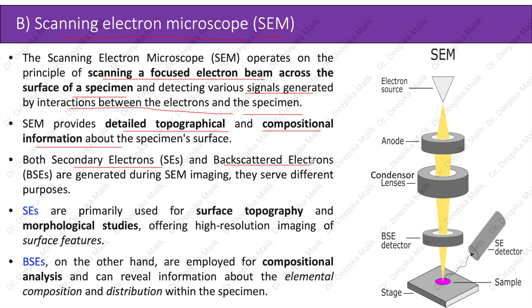Both secondary electrons and backscattered electrons are generated during SEM imaging, and they serve different purposes. In the diagram, the electron beam from the electron source passes through the condenser lenses, which condense it towards the specimen. From the specimen, secondary electrons and backscattered electrons are generated, for which we have different detectors — one for secondary electrons and one for backscattered electrons.